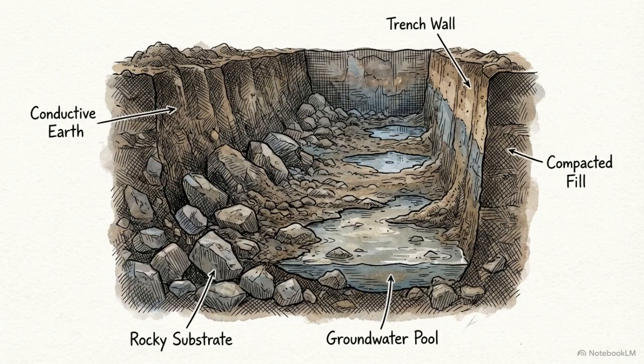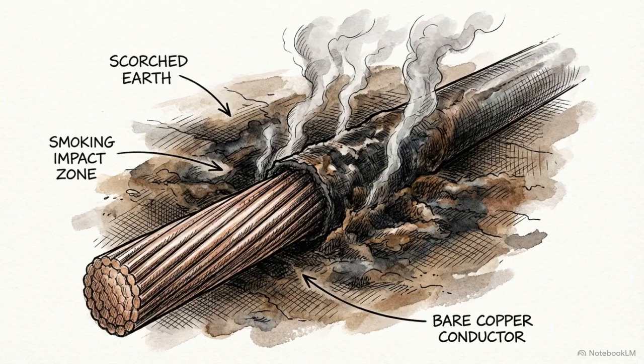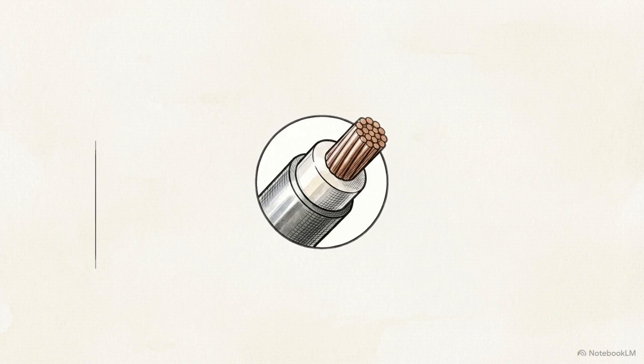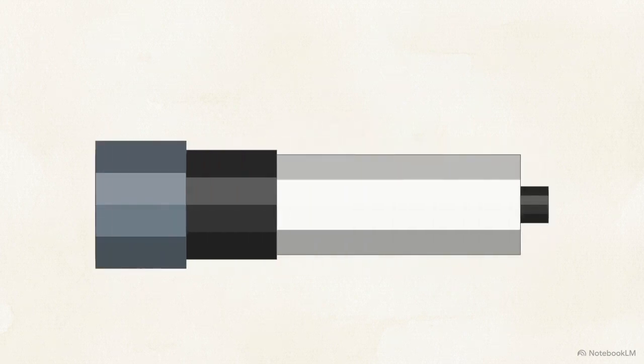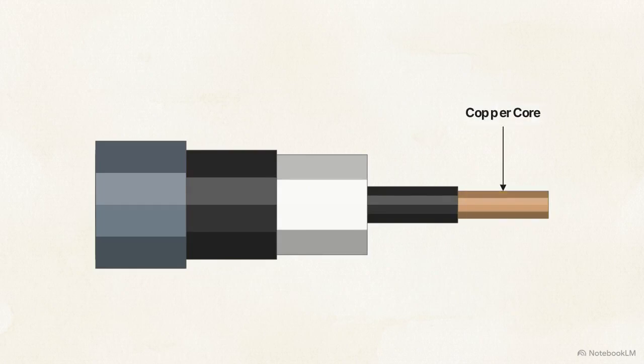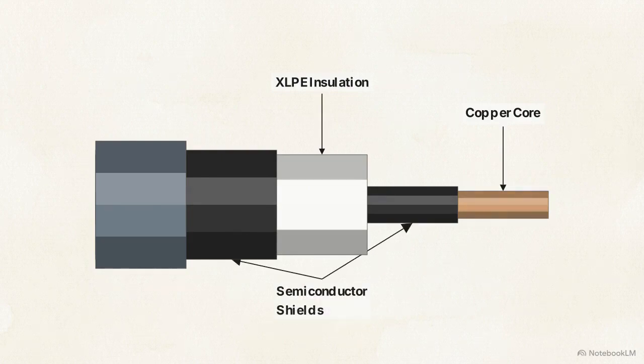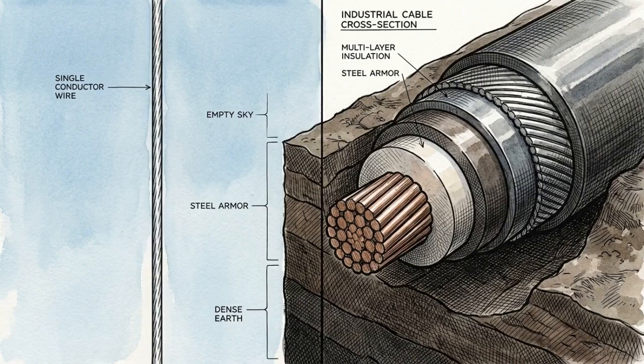Dirt and groundwater are highly conductive, meaning you cannot drop a bare wire into a trench. To keep the electricity from escaping, an underground cable has to manufacture its own isolation. This cross-section shows the required anatomy: a central copper core surrounded by thick cross-linked polyethylene insulation encased in semiconductor shields and finally wrapped in a metallic outer sheath. What takes a simple bare wire in the sky requires a highly engineered, multi-layered pipe when buried.